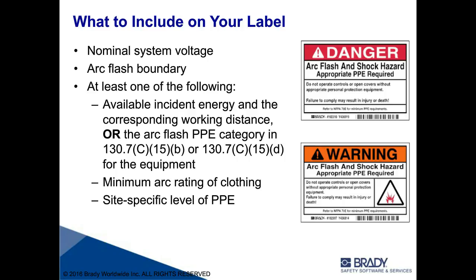The information there on the screen is an excerpt from NFPA 70E and shows what needs to be on there. Nominal voltage is pretty straightforward. Is your panel 240 volts, 208 volts, 480 volts? What's the nominal voltage of that equipment you're putting the label on? The arc flash boundary is also required. The arc flash boundary is the distance at which the incident energy is 1.2 calories per centimeter squared.